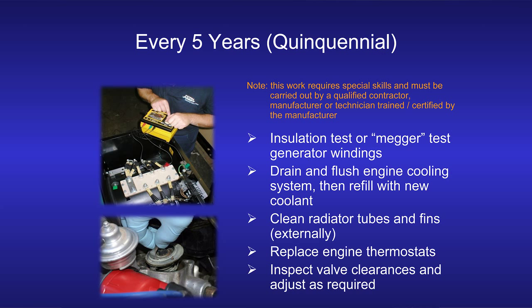And as I was alluding to earlier, every 5 years we have to do another set of inspections, which is more invasive, if you like, into the system. Megger testing the generator windings, which means we have to disconnect them from anything else outside the generator machine and put a high voltage on them to see whether the insulation of the windings is breaking down. Replace thermostats, adjust valve clearances, and flush the cooling system. I'm just going to go to the next one.